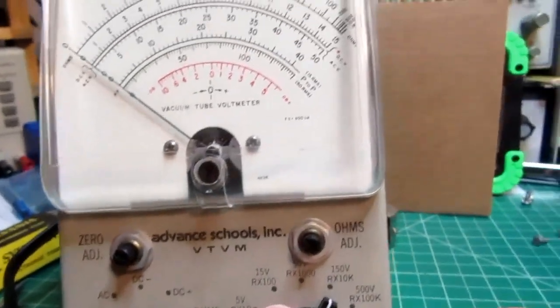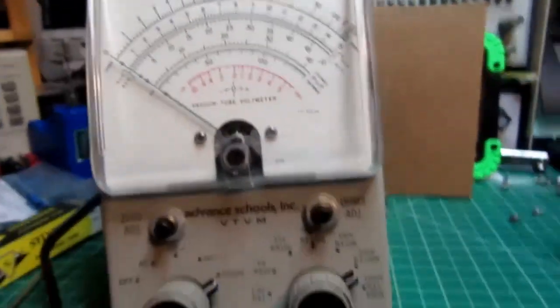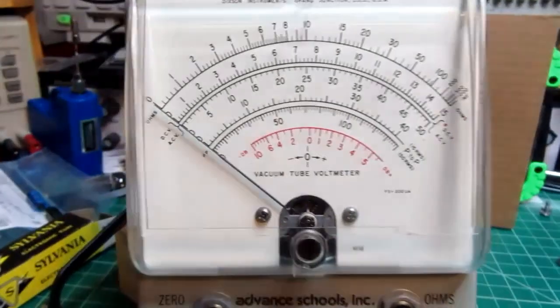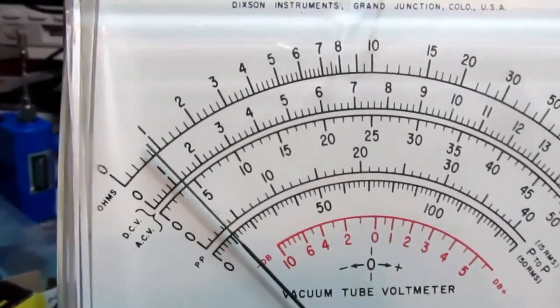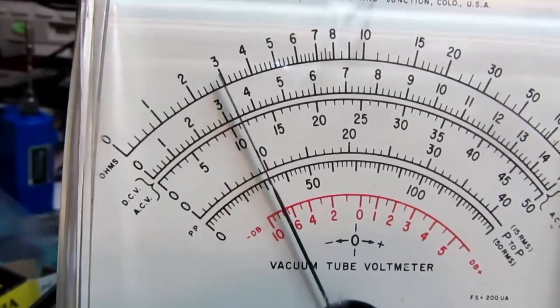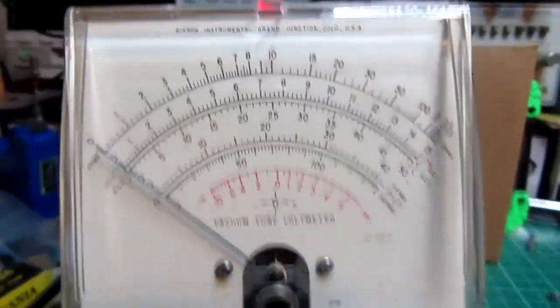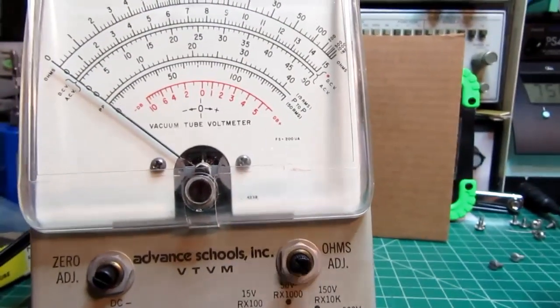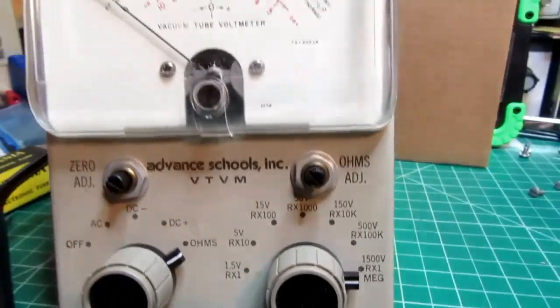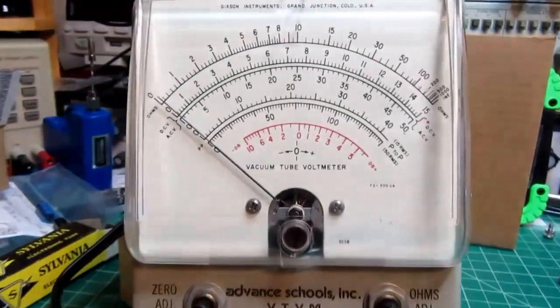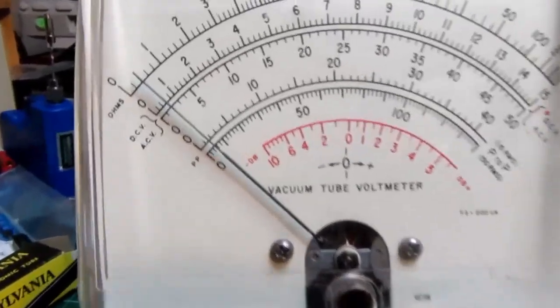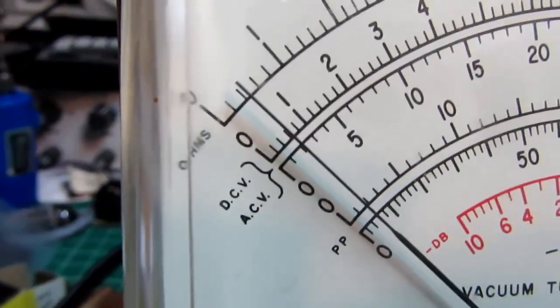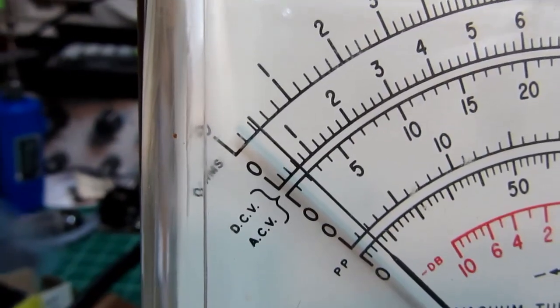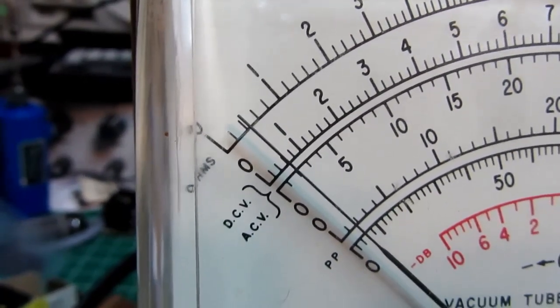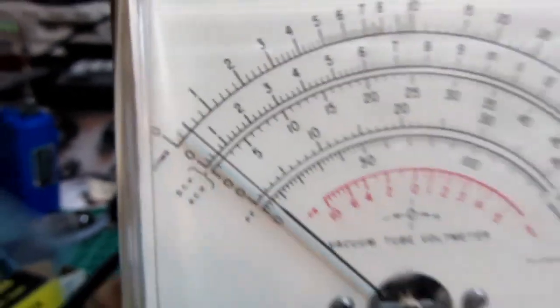Let me just go up to the R times 100K and dial in 100, 200, 300, 400. Yeah, it's pretty much in the ballpark. And then go to the meg, R times 1 meg, and 500K should give me about half of that. It's a little low, but these are not highly precision instruments. So we're about in the right place.